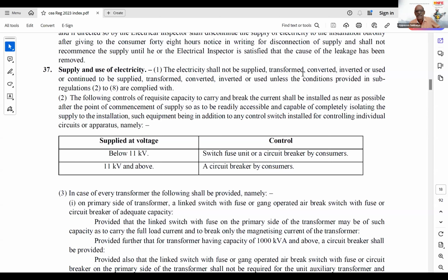for example, after the Uphaar Cinema theatre tragedy, overnight regulation came into existence where only dry-type transformers can be provided within multi-storey building premises. So these are the things regulators want to fine-tune, to avoid any part of the installation posing a hazard for the occupants. This is a specific regulation which is concerned with the provision of abiding by the standard by the consumers. I don't think an RMU or ring main unit can be relied upon as a right of way the consumer can have. It's a fireman's switch. Your own breaker can be a fireman's switch for your installation in case of emergency.